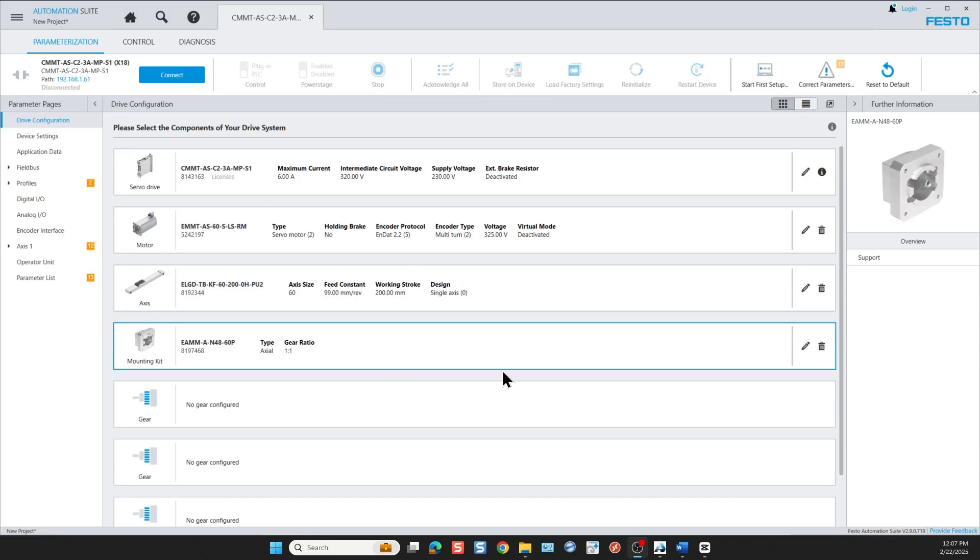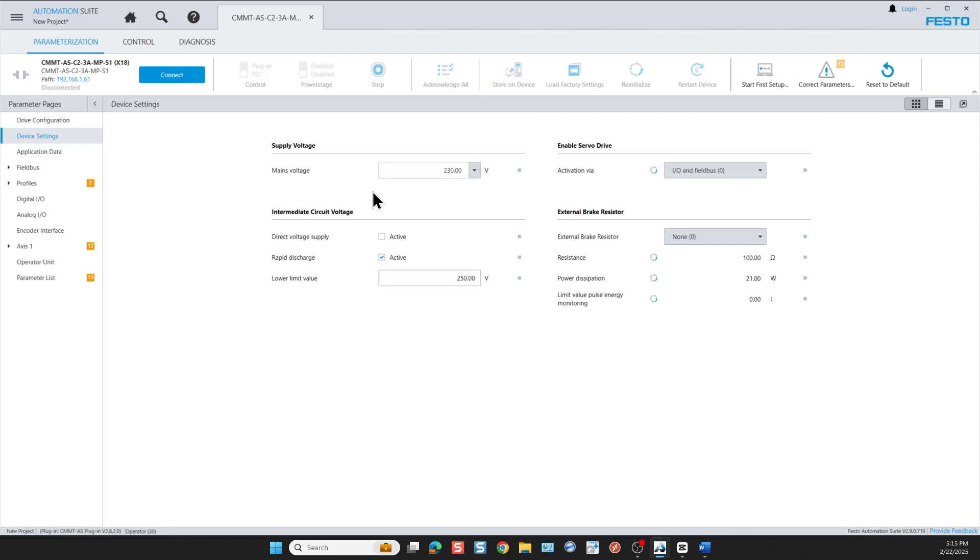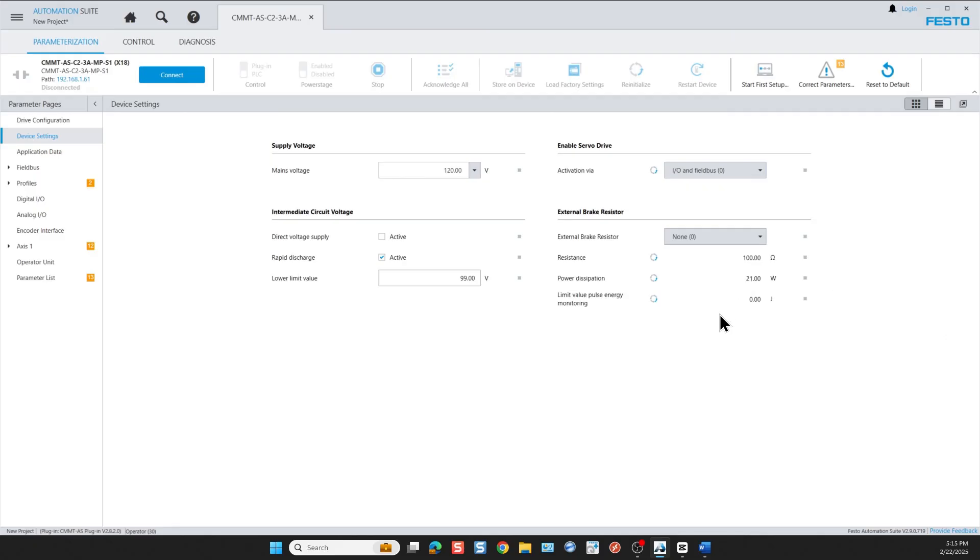Now let's work on the device settings. In my case I'm only using 120 volts, so I'm going to modify this for intermediate circuit voltage. I select 99 volts. I'm not using any external brake resistor and I'm going to keep IO and fieldbus for the activation of the enable signal.